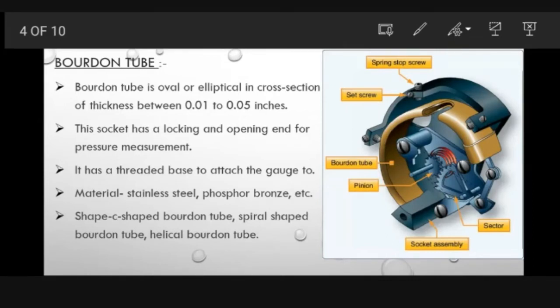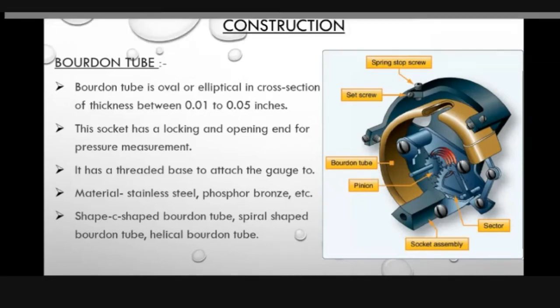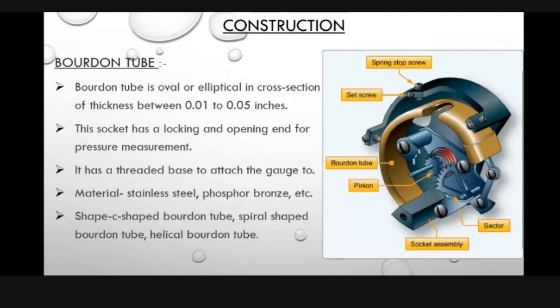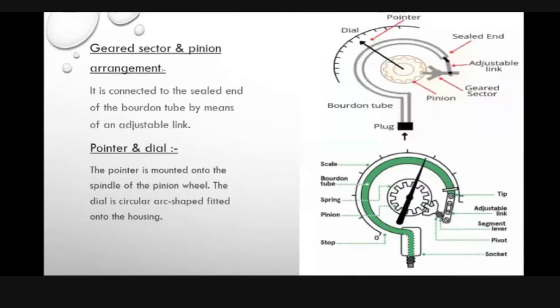The next part is the sector and pinion. The free end of the Bourdon tube is attached to an adjustable link, which in turn is connected to a sector and pinion. To the shaft of the pinion, a pointer is connected, which moves over the pressure calibrated scale. Pooja, next.